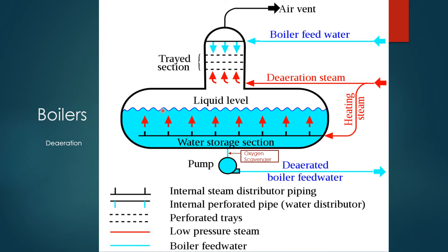This is the steam distributor piping, and this indicates the trays. The steam line and boiler feed water are maintained here. This is a pressure-type deaeration; another type is vacuum-type deaeration, in which the boiling temperature is lower. Mostly the pressure-type deaeration is used, as it heats incoming boiler feed water to around 106 to 108 degrees centigrade, which improves fuel efficiency.